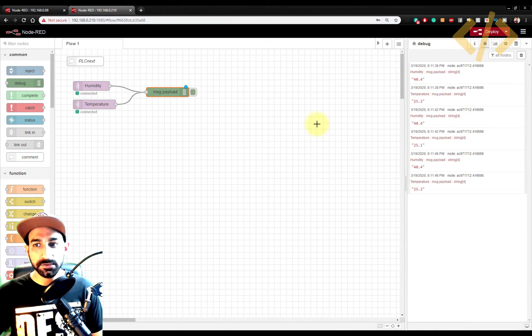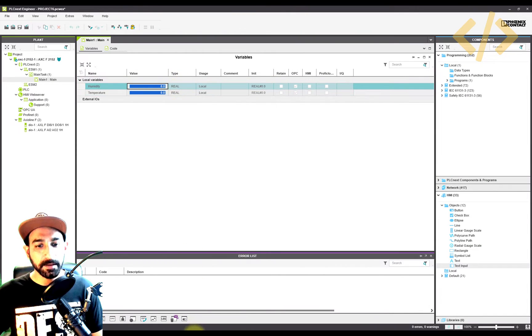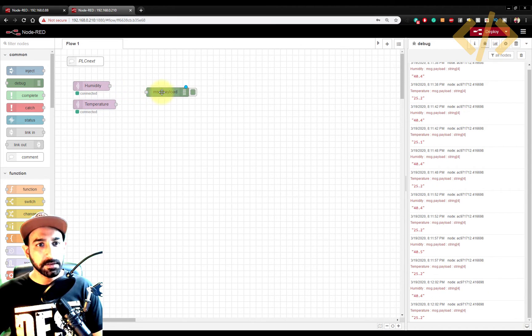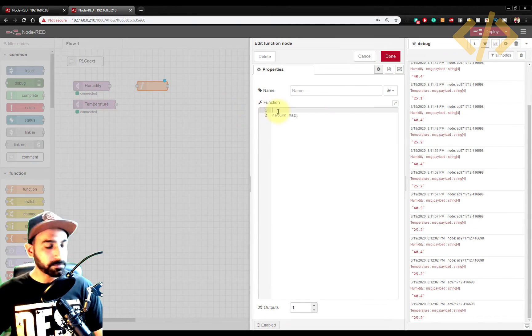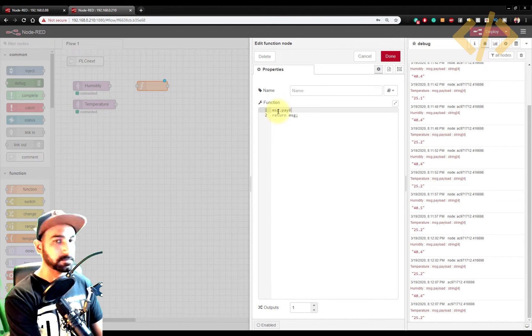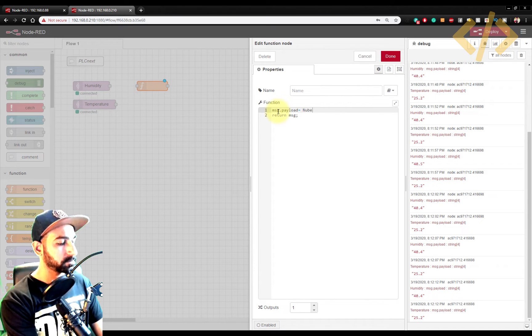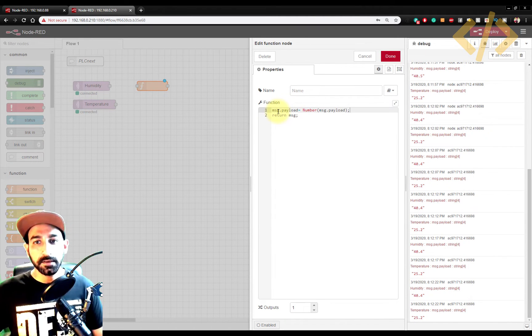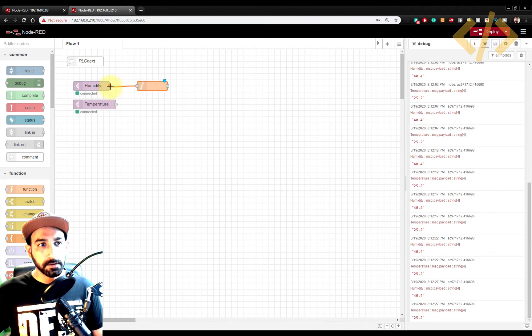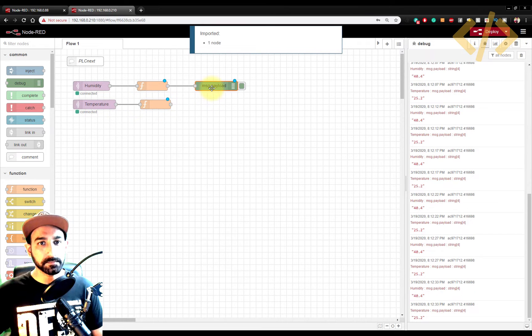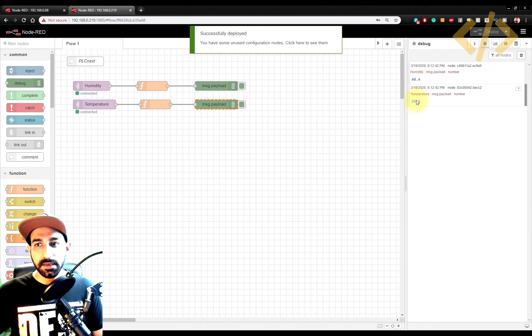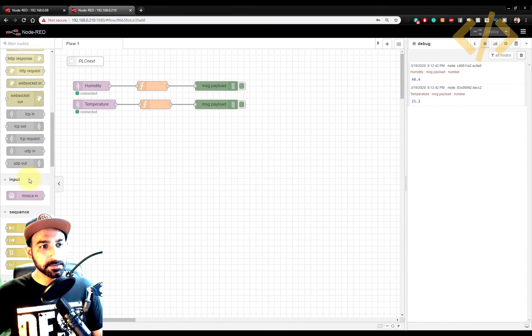These are reset now. We want to push these two values into my PLC. If you notice, the PLC expects a real number but here you are getting a string, so you can convert from string to number. I'll take a function node and write 'msg.payload = parseFloat(msg.payload)' — click done. I'll put it in the flow with a debug node and do the same for temperature. Now we have these two as numbers: 40.4 and 25.2. Perfect.